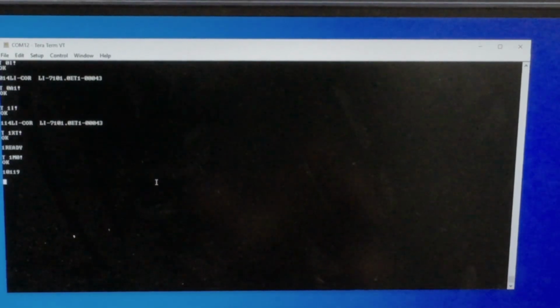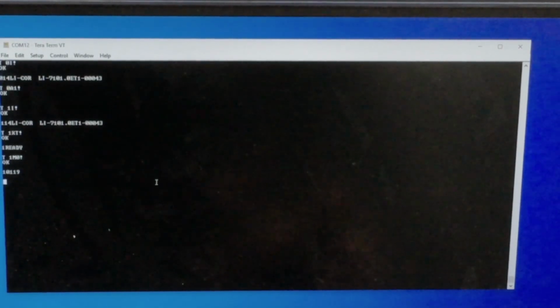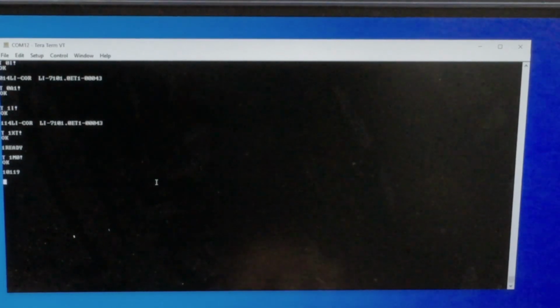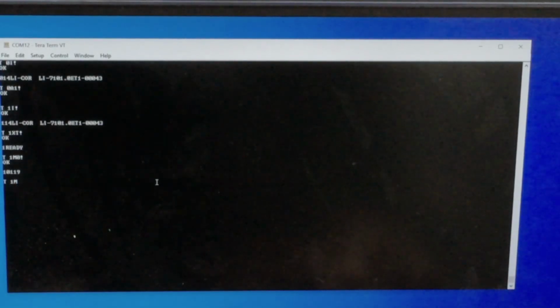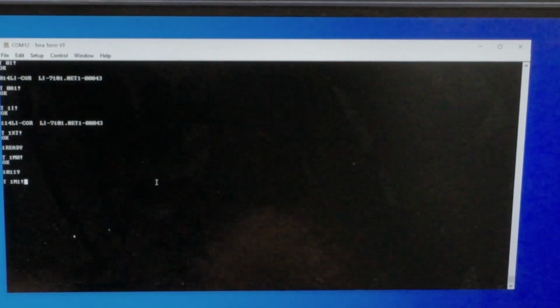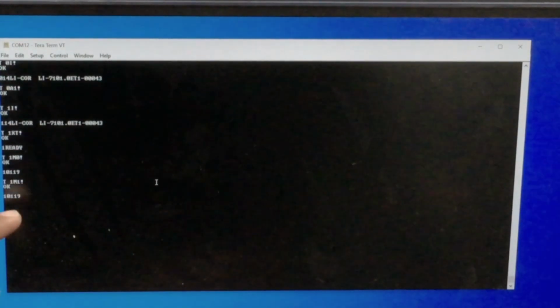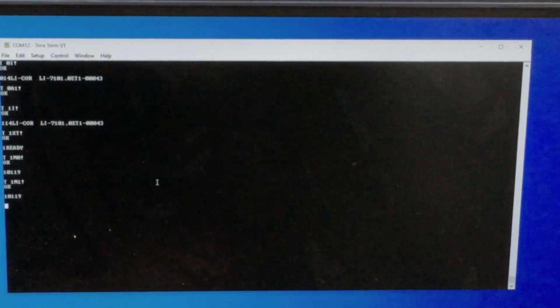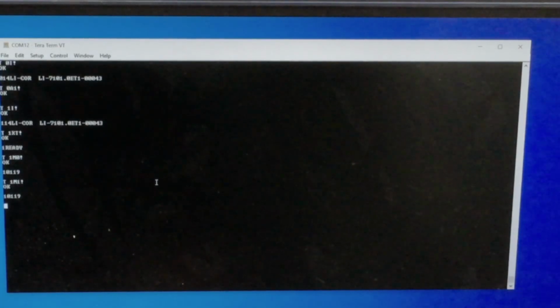In this sensor, in this adapter I have, when I send the M command, I have to follow through with the D commands to get the different outputs. So if I send the M command - in this case an M1 command - I get back the address, the 11 seconds I have to wait till I get the outputs, and 9, which is the number of variables. So to get the 9 variables, I still have to send a series of D commands.